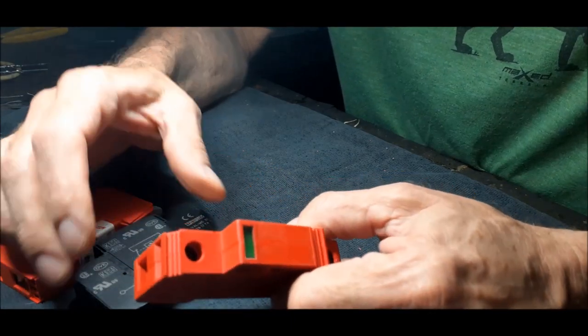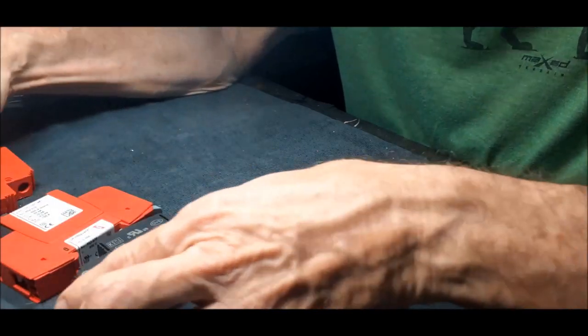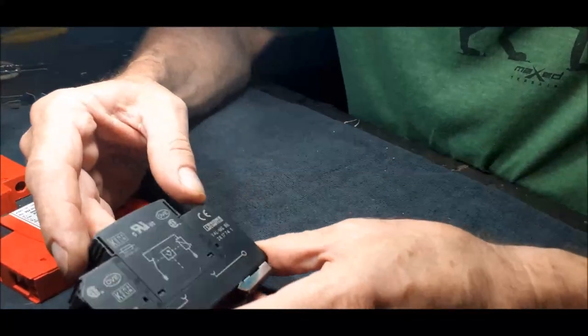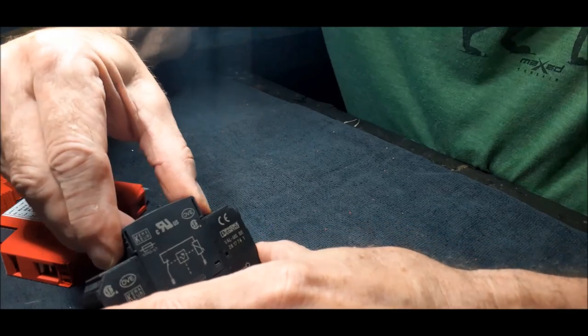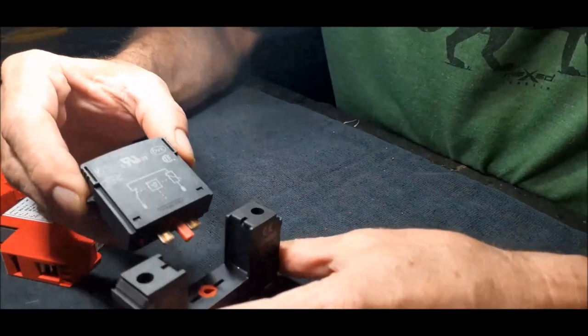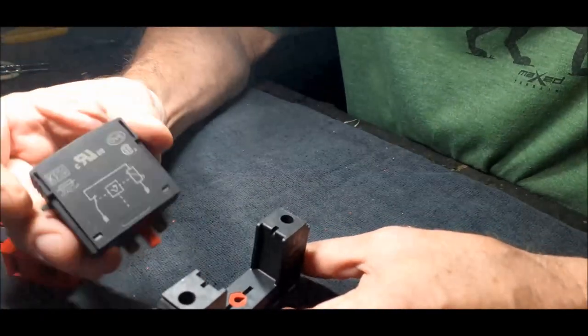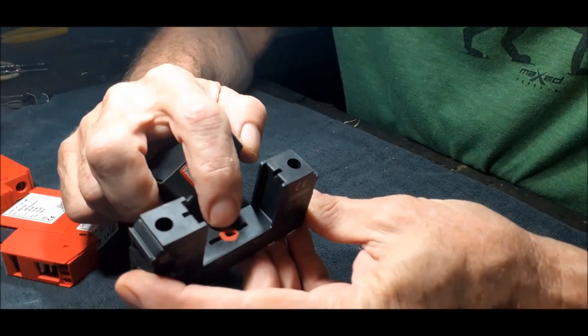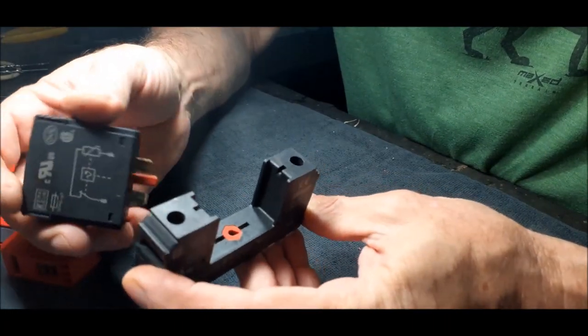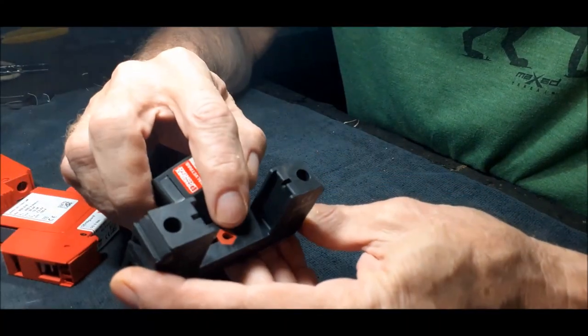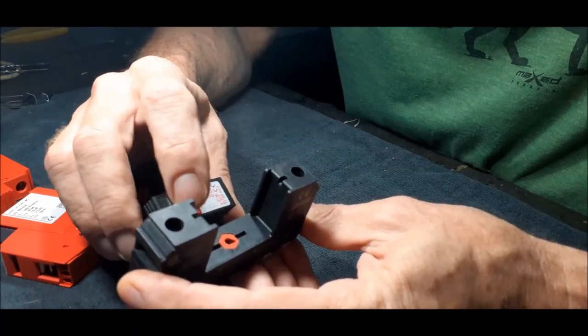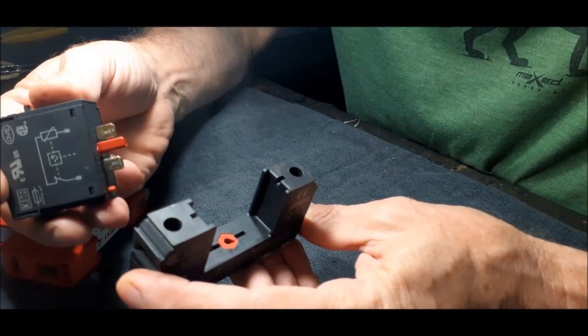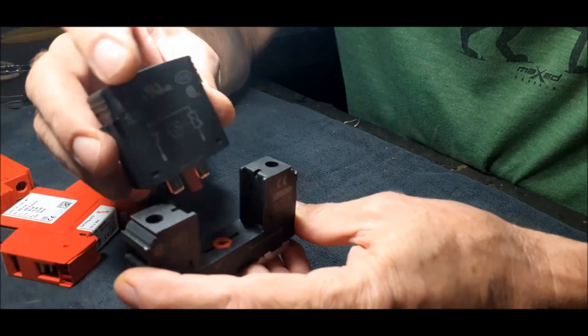Let's check the other types here. This is a Phoenix one, but this is removable. There's a base. You can unplug the cartridge. They call it a cartridge. There's like an indicator for different voltage types so that you don't put maybe a 275 volt in a 600 volt application.